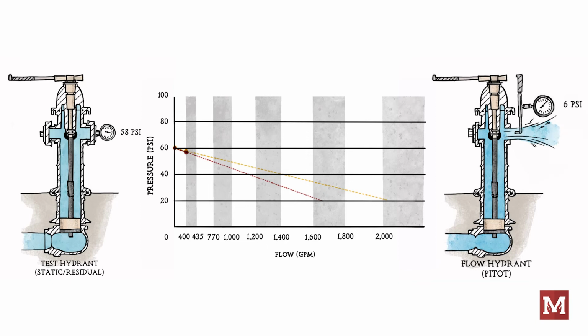Now let's take that same small deviation and look at a second test where we are flowing, let's say, about 1,000 GPM. So let's say we again slightly misread that bouncing needle and overestimate our residual pressure again by 1 psi. So in the test that has 1,010 GPM, we read a residual pressure of 45 psi instead of 44 psi. Let's plot and draw this new curve.